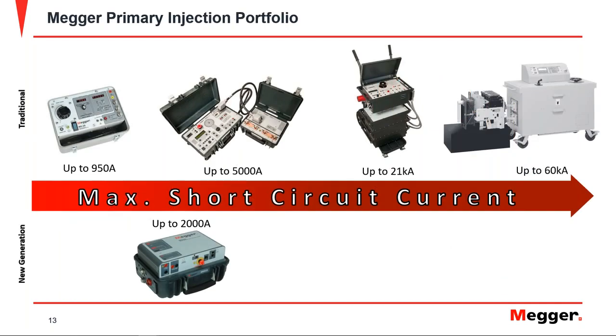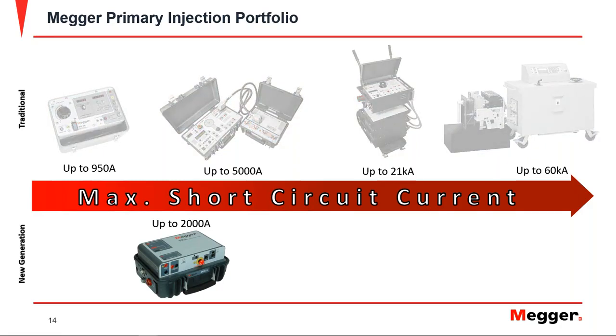As I mentioned, we're going to focus today on the SPI 225. I also wanted to show that we offer a very wide portfolio of primary injection units. I'm only showing a few of the available instruments on the slide. As you can see, we go from units that can deliver up to about 1,000 amps all the way up to 60,000 amps, for low and medium voltage breakers with higher nominal currents. Again, we're going to focus on the SPI 225, which can give us up to 2,000 amps for instantaneous testing. And as I mentioned, it is part of the new generation of primary injection units from Megger.